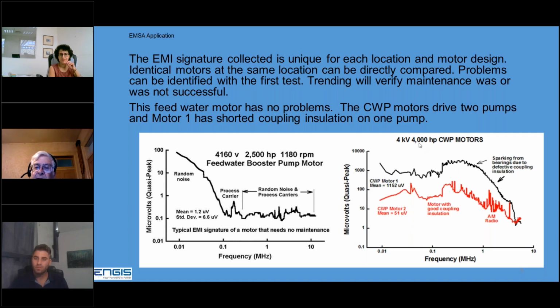These two 4 kV motors are at a big coal-fired plant. It has a motor in the middle and then a pump on both ends of the motor. So there's 2 pumps and 1 motor. You have to have insulation on that shaft or you'll get circulating currents. Well, the number 2 motor is running properly. Here's a power line carrier off a transmission line system. More data carriers. Here's the AM radio down there.